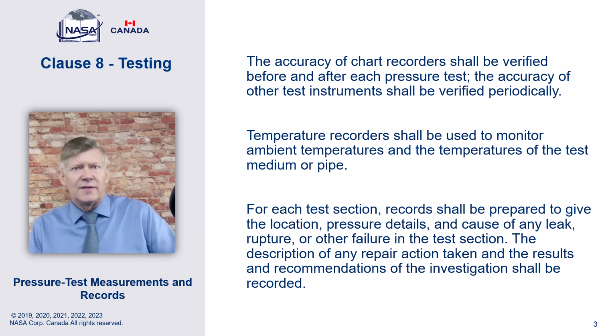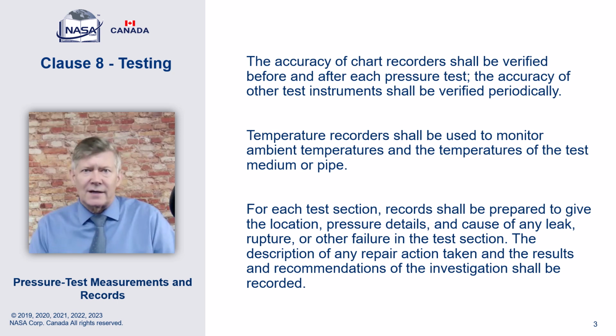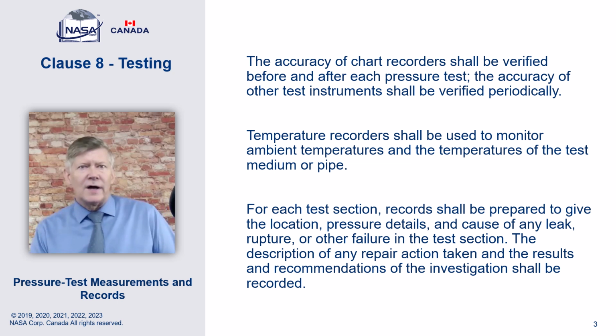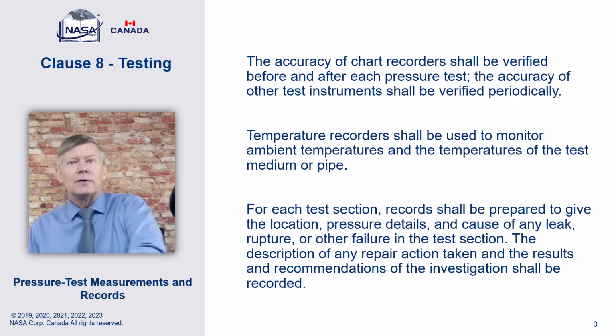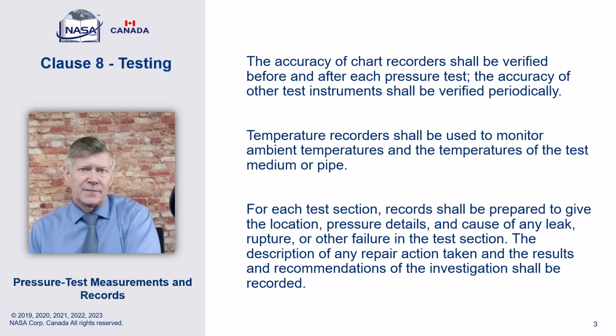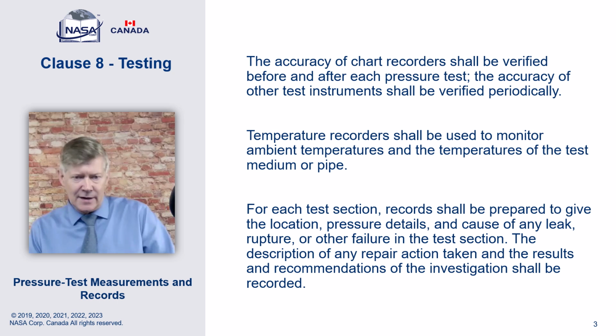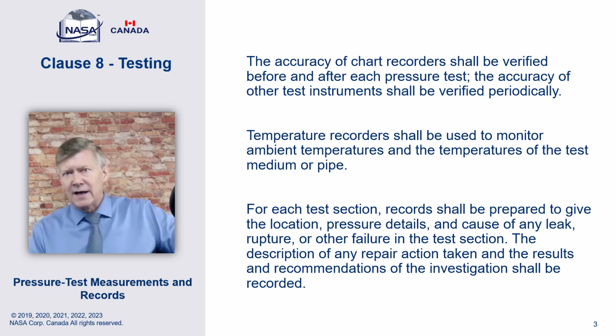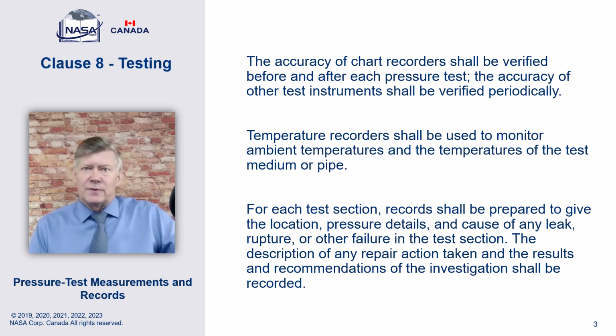They adjusted it and they are now returning it to me reading correctly again. The problem I've got is I don't know when did it go 10% out. Did it go 10% out after the first test I used it on, or was it fine the whole year and just went out on the last test, or even during shipment to the calibration laboratory? So because I don't know that, I now have to look at every test that I did and determine would a 10% variance spoil that test. And for anywhere where that 10% variance would spoil the test, I'm going back to retest.